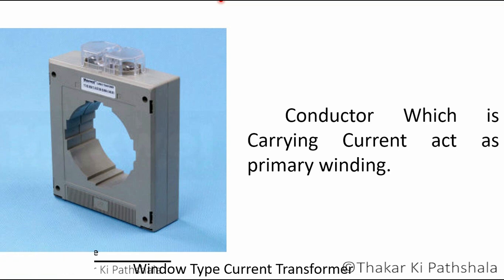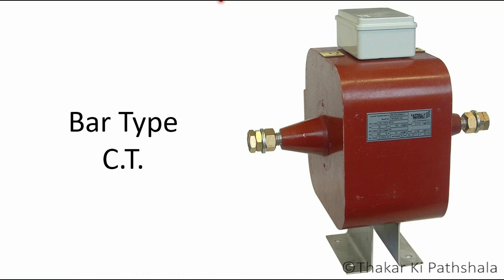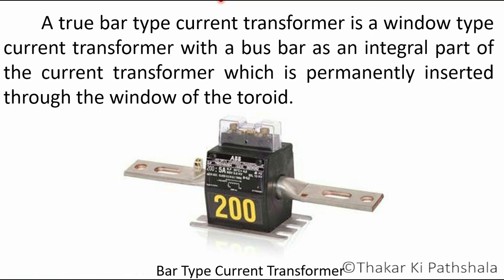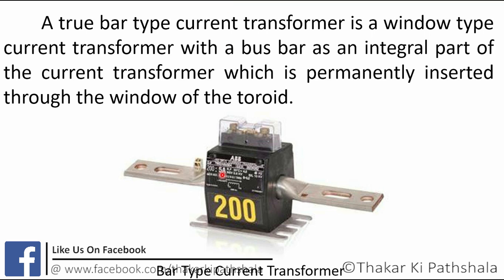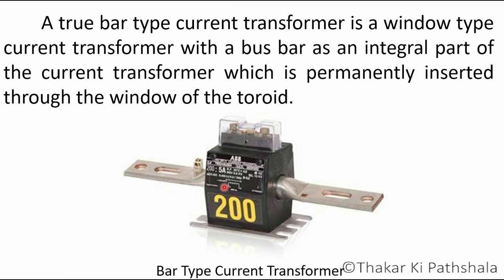Now it's time for final type, which is bar type. There is not much difference between bar type and window type current transformer. You can see from the image that only difference is that a true bar type current transformer is a window type current transformer with a busbar as an integral part of the current transformer, which is permanently inserted through the window of the toroid. Here busbar serves as a primary conductor.